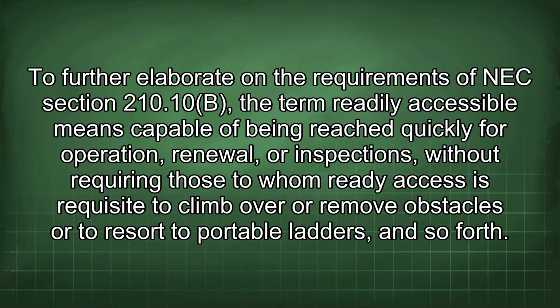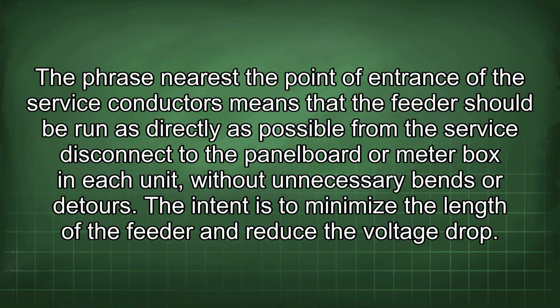To further elaborate on the requirements of NEC Section 210.10(b), the term readily accessible means capable of being reached quickly for operation, renewal, or inspections, without requiring those to whom ready access is requisite to climb over or remove obstacles or to resort to portable ladders, and so forth. The phrase nearest the point of entrance of the service conductors means that the feeder should be run as directly as possible from the service disconnect to the panel board or meter box in each unit, without unnecessary bends or detours. The intent is to minimize the length of the feeder and reduce the voltage drop.